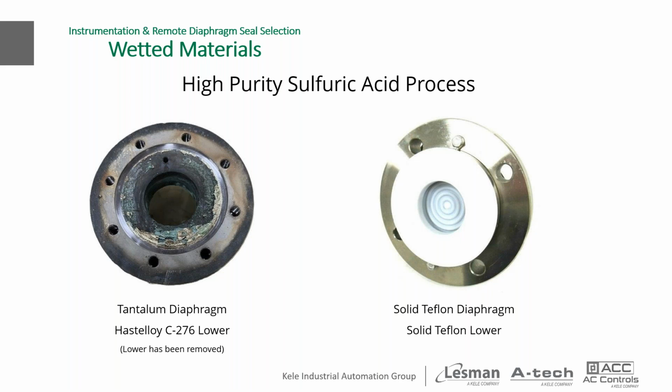This particular application was frankly very good business for us. Every 6 months or less, they would order a new batch of pressure seal assemblies. These are actually on pressure transmitters. So after a few years of doing this, they came back to us and asked if there was a better, more durable solution. The photo on the right shows a solid Teflon diaphragm and a solid Teflon lower.